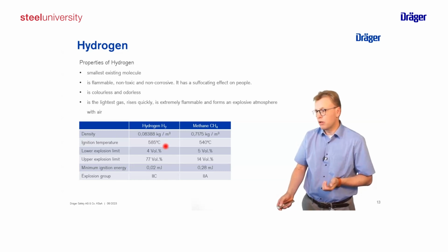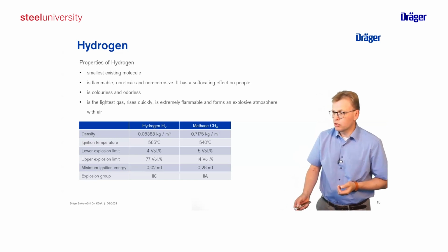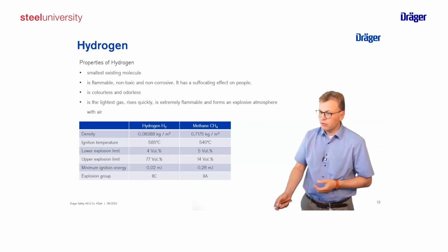Also about lower explosion limits. So it means at which point you have an explosive atmosphere, which in combination with an ignition source will lead to an explosion. But what differs already is the upper limit, that means the range to where the gas is dangerous, so can form an explosive atmosphere. So we see 77 compared to 14 volume percent. But the highest risk is the amount of energy we need to ignite it.